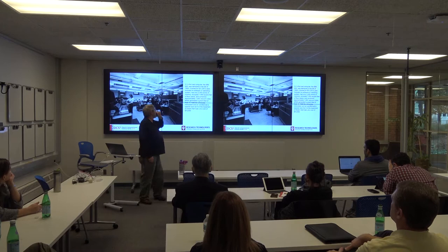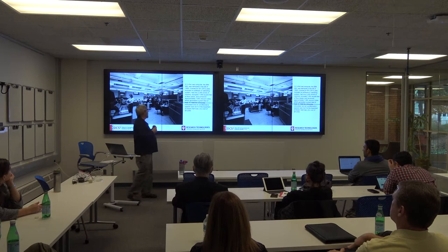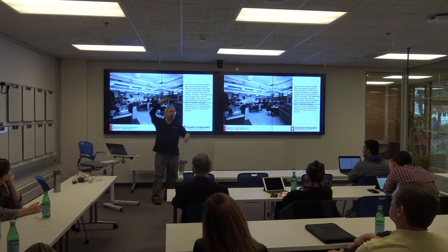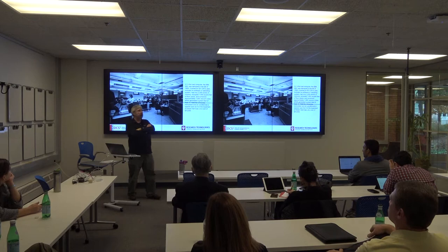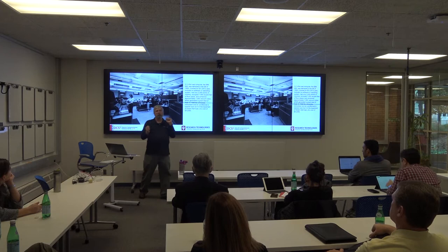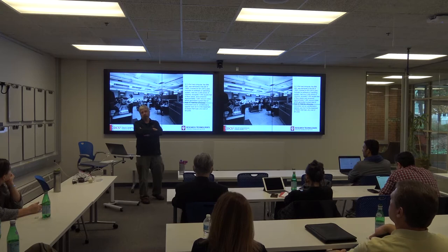But we were talking with a vendor yesterday about what the next cluster here at UC might look like. And I swear, one third of the conversation was about heat and power and what it was going to take, and what form we could put it in that facilities here could handle. So we're still fighting that battle. Some of these computer racks, if you've ever seen one, are about 20 inches wide and about yay high. A lot of those pull about 18 kilowatts. Your house sitting on the street pulls about 1 kilowatt on average over a 24-hour period, even though turning on an electric stove is a bit more. So one rack the size of a refrigerator is pulling the equivalent of 17 or 18 houses. That's pretty much both sides of a block. The newer technologies that are coming out pull double that, about 30 to 35 kilowatts.